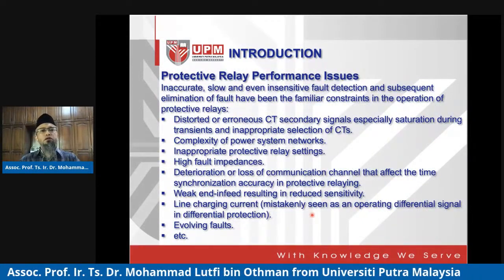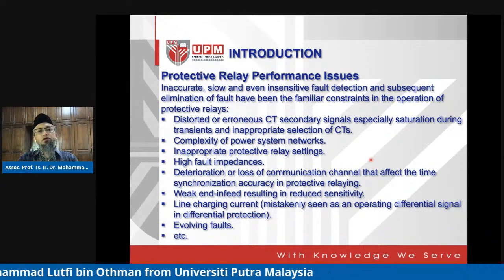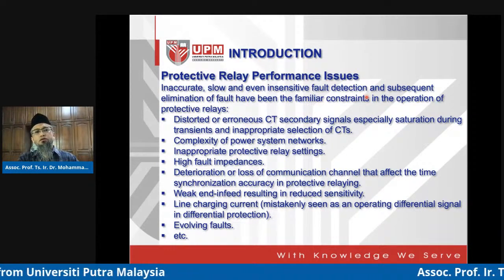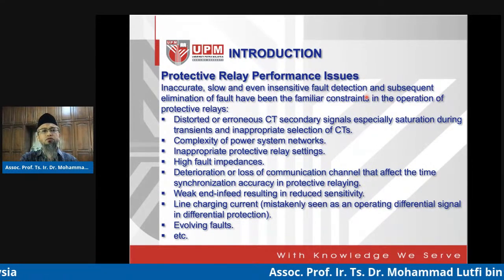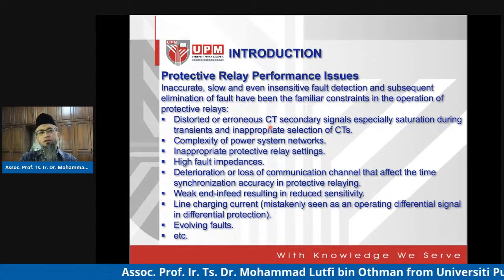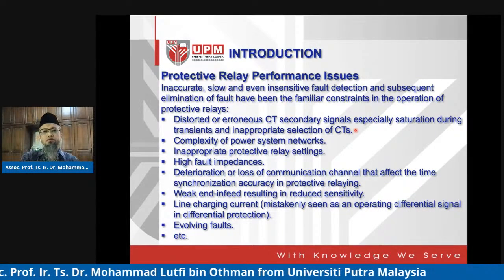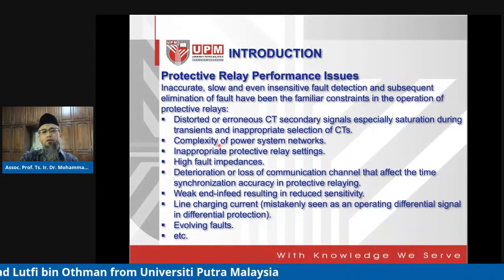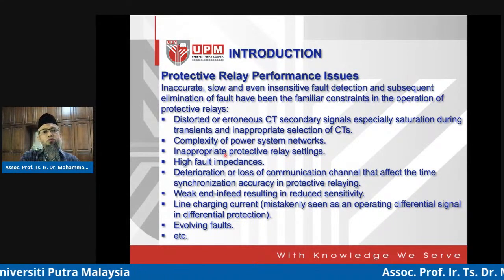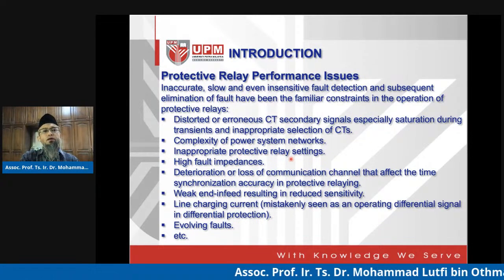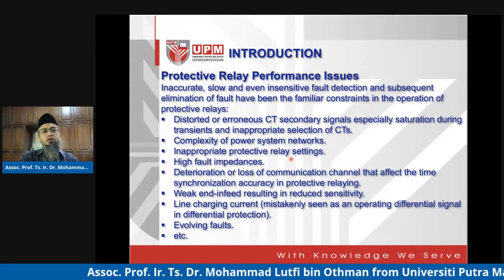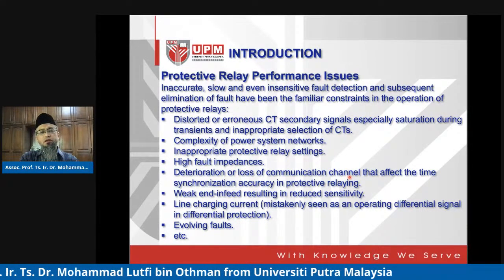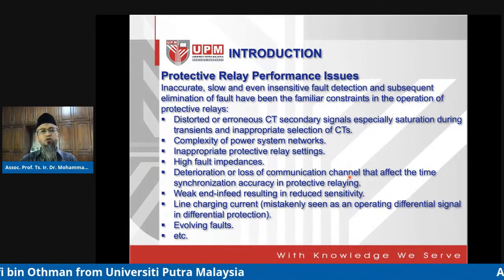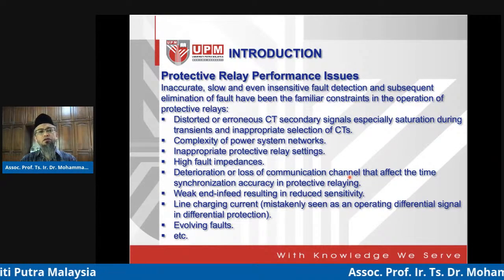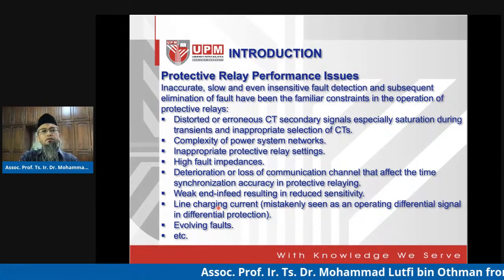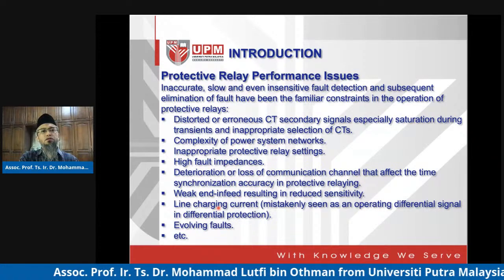There are issues with protective relay operations. Inaccurate, slow and even insensitive fault detection and subsequent elimination of faults have been familiar constraints in the operation of relays. For example, distorted or erroneous current transformers, or even potential transformers, or sometimes we call them voltage transformers, VT. And then the complexity of power system networks, possibly inappropriate protective relay settings, high fault impedances, deterioration and loss of the communication channel that we normally use nowadays for coordinating the operation of various protective devices, and so on and so forth. So there are quite a number of issues that you may come across.